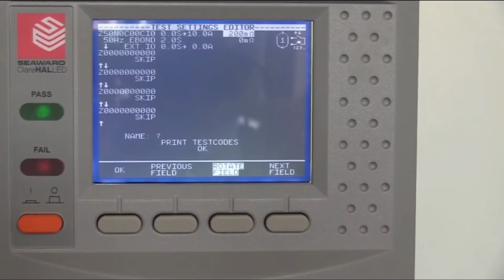There we go. We can put a lower limit in. As for all tests, we can set both upper and lower limits. So if you do have any kind of quality measurement and you want to be absolutely sure you're getting the correct amount of cable, we could set a lower limit. We can also use upper and lower limits to confirm correct test procedures.